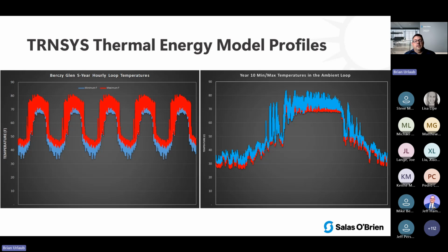And then, of course, the beautiful thing about, in my opinion, these single pipes with distributed thermal assets is that you don't get the thermal creep in some of the bore fields you would have as, let's say, a campus where you've got one large bore field with 600 bores, and you've got all those in a grid pattern. And you're going to definitely have a little bit more impact to the center of that grid by putting heat in or taking heat out.